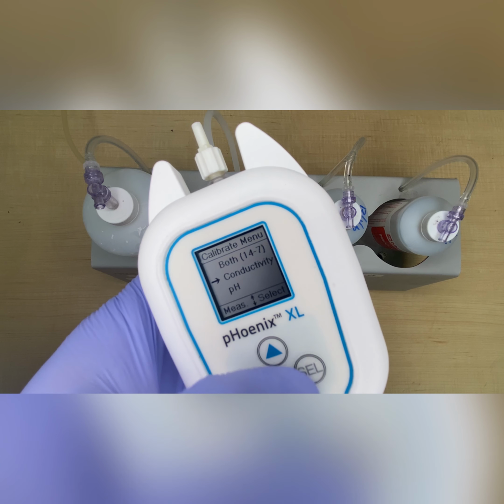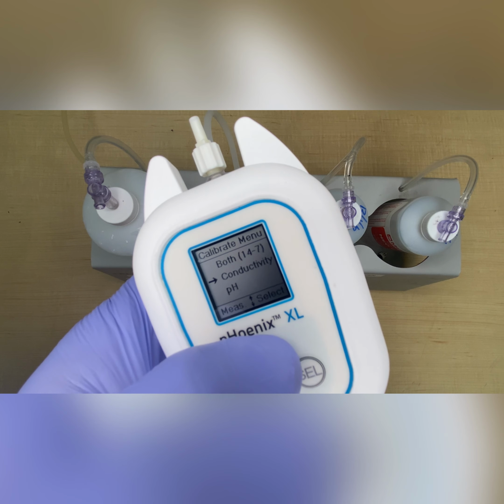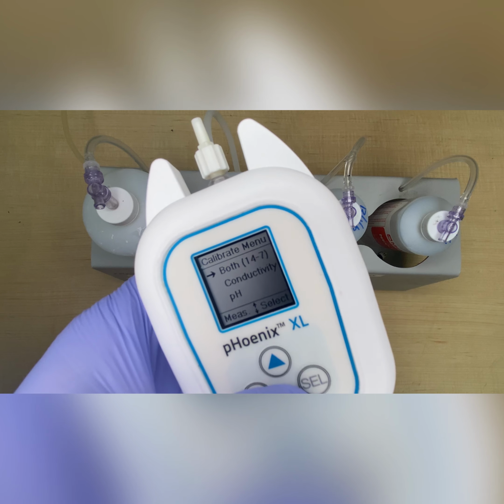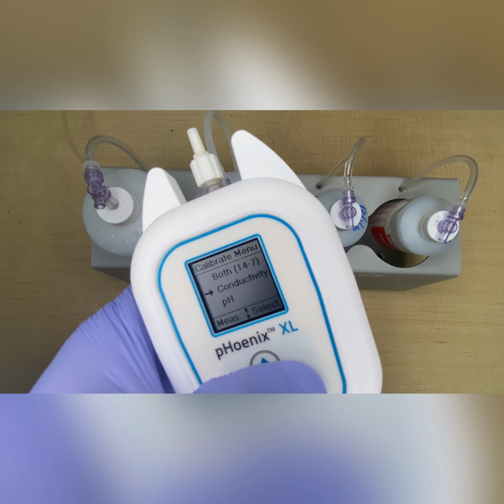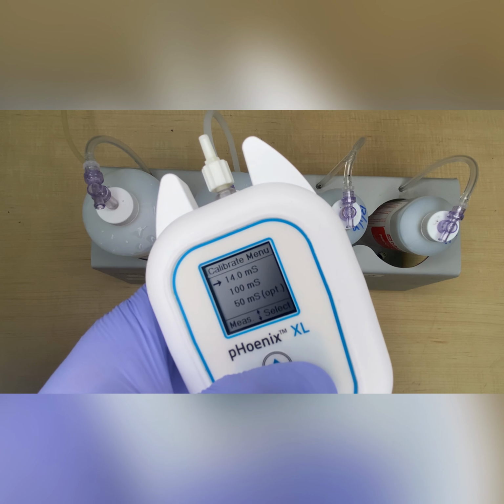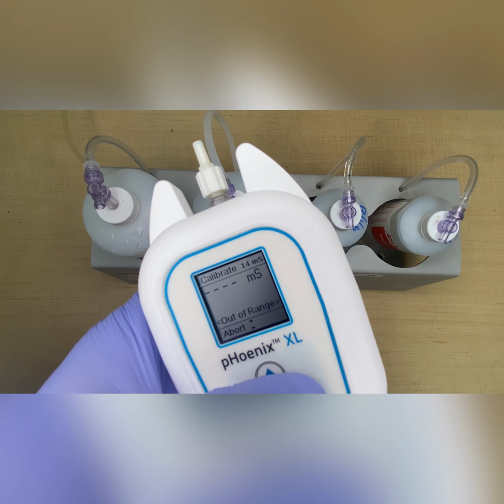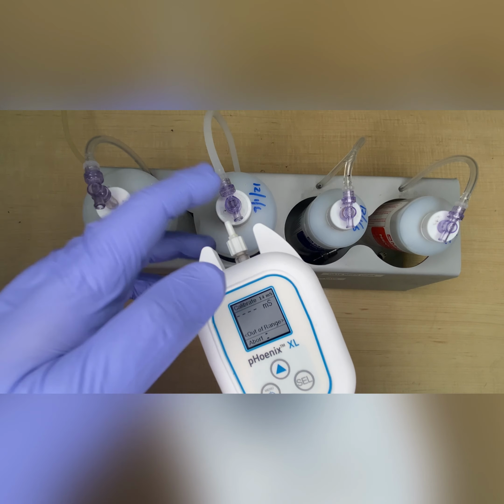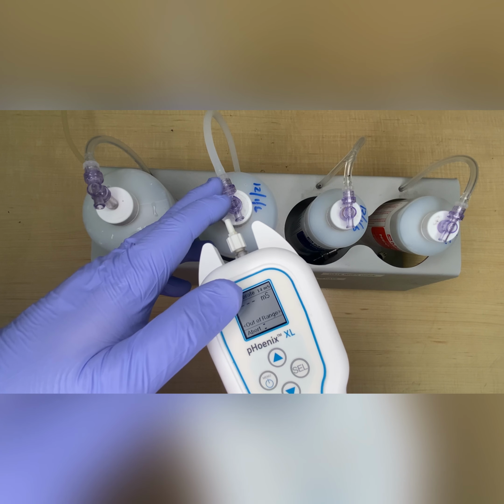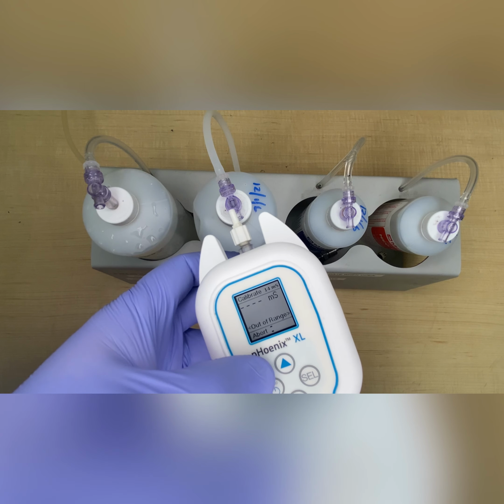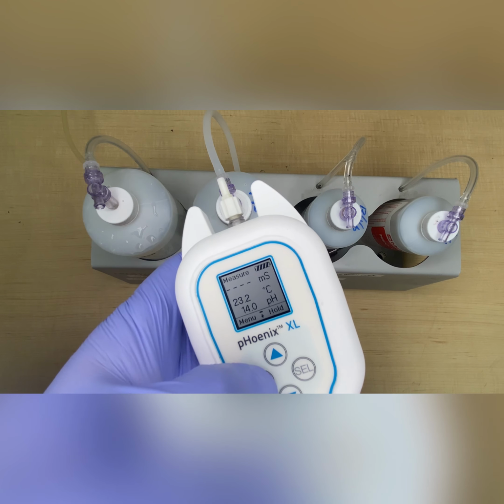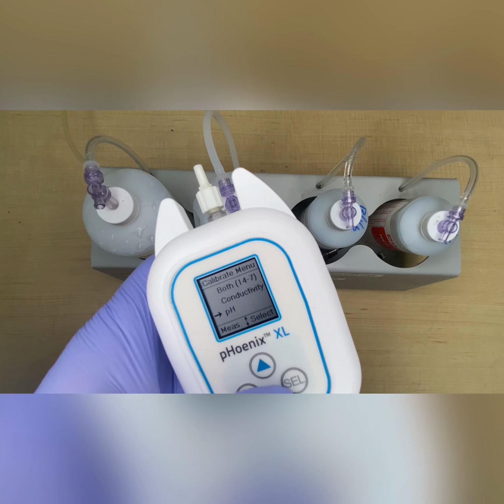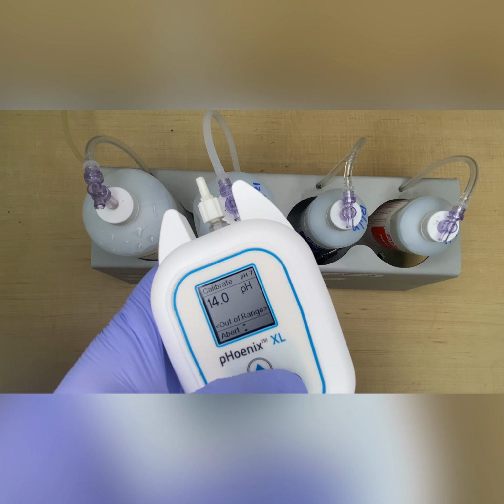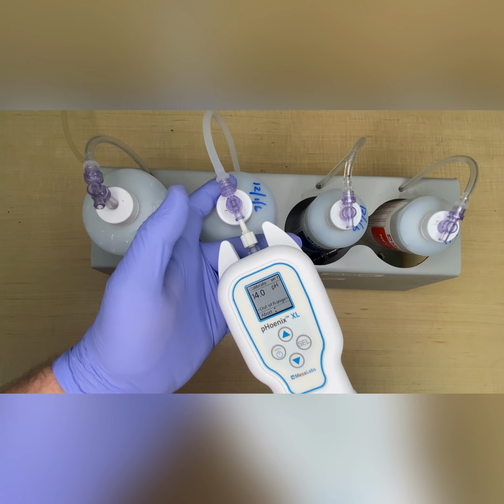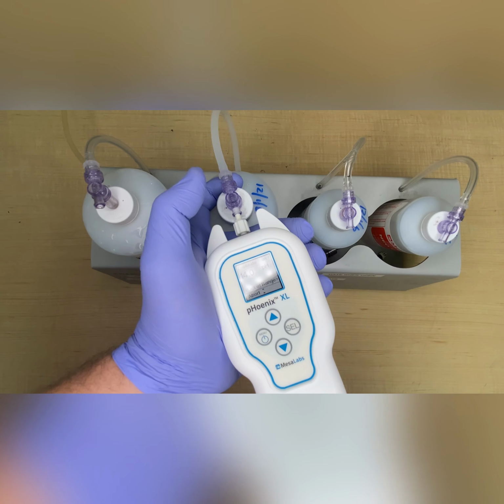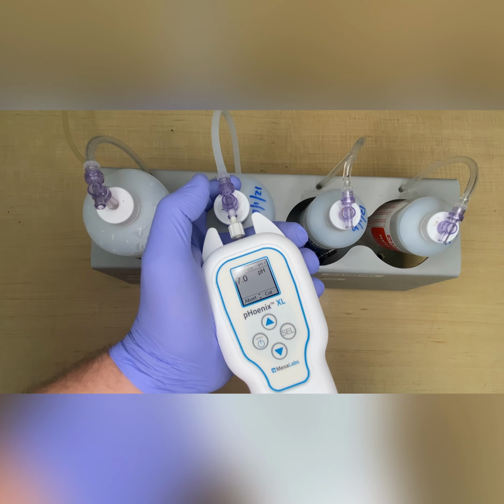Next up, we're going to walk through how to calibrate separately. So you're going to go back into your calibration screen. You're going to go down and select conductivity. You're going to select high, and you're going to select 14.0. And then you'll pull your solution up like you did before. Get your calibration key and save. Then you will go back out to your main screen and go back in, calibrate, go down to pH 7, and you'll pull your solution through again, wait for your cal key, and then you will select save.